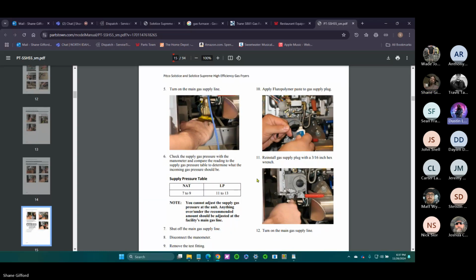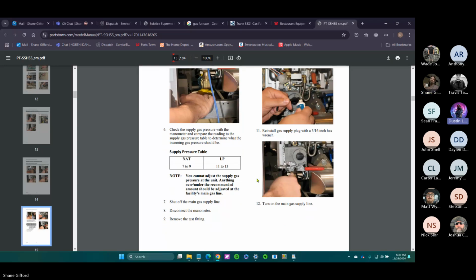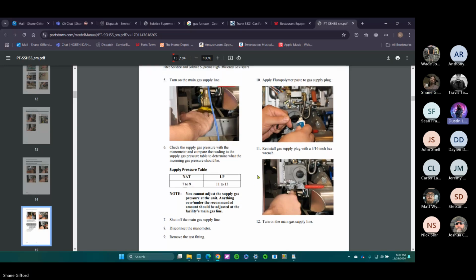So I know we do work at Freddy's too. In there, those turbo fryers are something different, way different than the Pitco. So just keep that in mind too. But a lot of times that exhaust will get plugged up if they're always dirty. Everyone says they clean their fryers and they clean behind them, and we all know they don't. So make sure you check the exhaust too and clean out any debris. Sometimes food falls back behind there, and if it can't exhaust properly, it's just going to build up heat a lot quicker and trip that high limit.